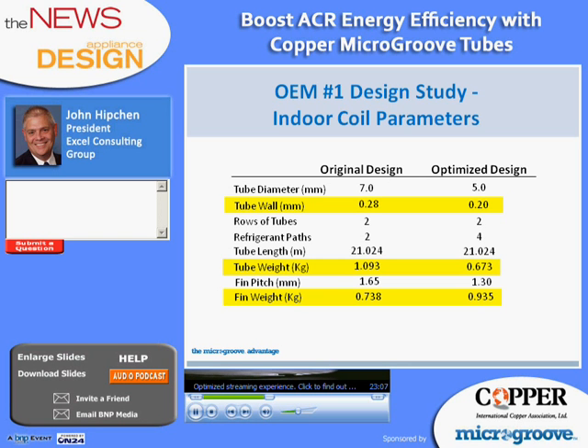Although those numbers are the same for each design, the optimized design uses smaller diameter tubes, 5 millimeter versus 7 millimeter. And we see a considerably smaller tube wall in the 5 millimeter tube than the 7 millimeter. The result here is 420 grams less copper in the optimized coil. And a quick look at the fin pitch tells us with the tighter spacing of the smaller diameter tubes, we have a denser coil with slightly more aluminum in the optimized design.